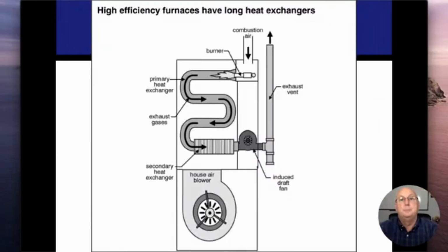High efficiency units and where they start and how they absorb the heat. Typically, there's going to be two heat exchangers on these. One is going to be our primary heat exchanger, and that's going to be this looping one. And that's going to be the pipe that comes down this way. This is going to be our primary heat exchanger. Then it goes into a radiator coil, so it's a much narrower tubing, kind of like an air conditioning coil that goes on there. And that's going to be absorbing the secondary one.